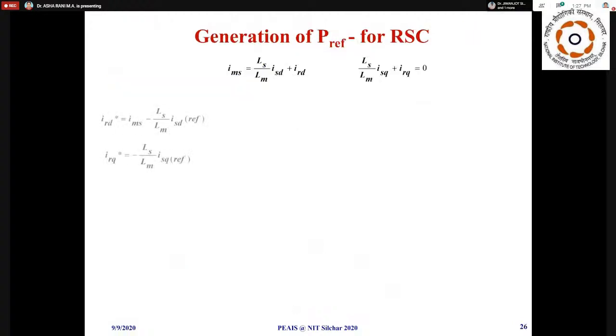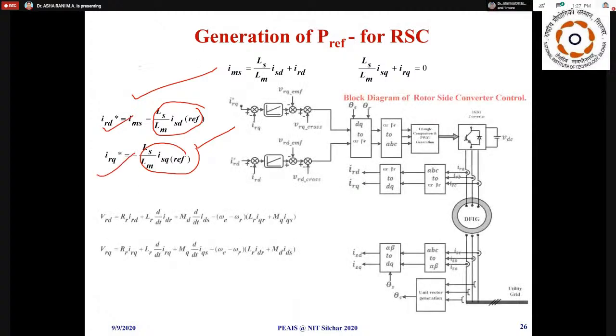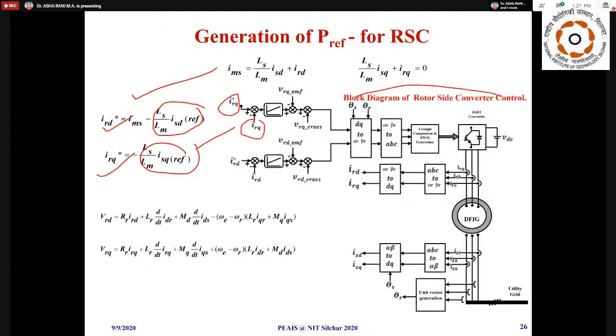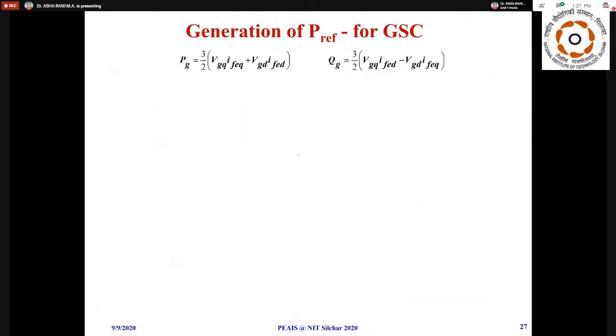Using this, I can find out what are the stator currents ISD and ISQ. After finding that, there are fundamental machine model equations for the rotor. Using that, by giving these two currents we just found, we can fix the reference rotor currents. By feeding this information to the control loop, which has the IGBT and other controllers seen earlier in the picture, it will pump this much power without taking anything from the grid.